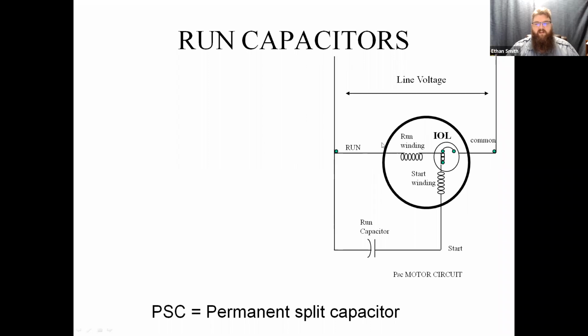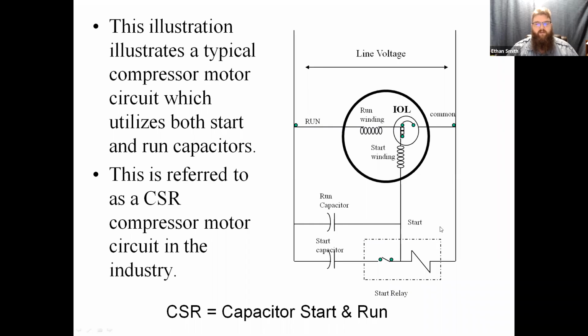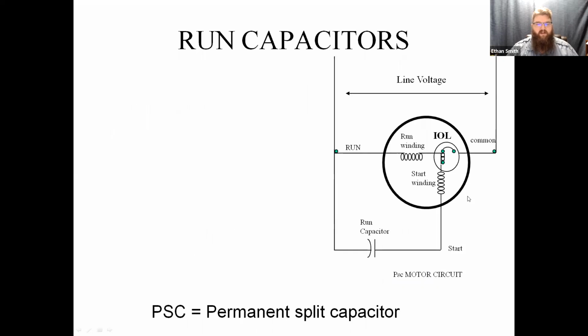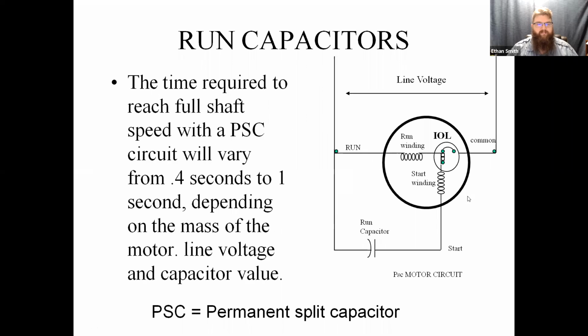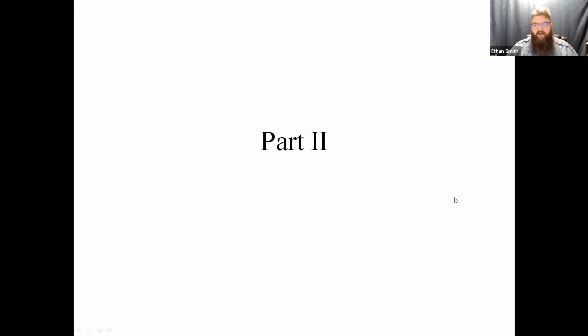And then of course we've just got our standard run capacitor. So this run capacitor would be doing double duty as a starting torque capacitor and an efficiency capacitor, whereas this one we can use a big capacitor to give it a big hit of torque on startup, and then have a run capacitor for efficiency once it's spinning. Okay. Any questions, guys?